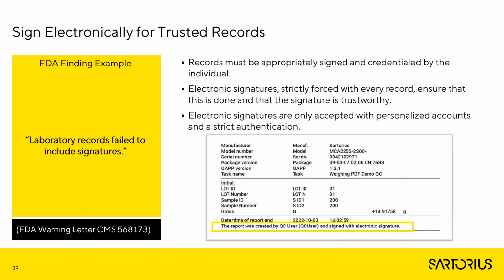Okay, the following violation is about reports that were not signed and therefore are not assignable to an individual. This can be prevented very easily if the system forces electronic signatures before a report is created. Along with very strict passwords and personalized user account settings, you then have proof and a clear assignment to each record. This is an example of how a digitally signed report looks on a Cubis II balance. Next slide.